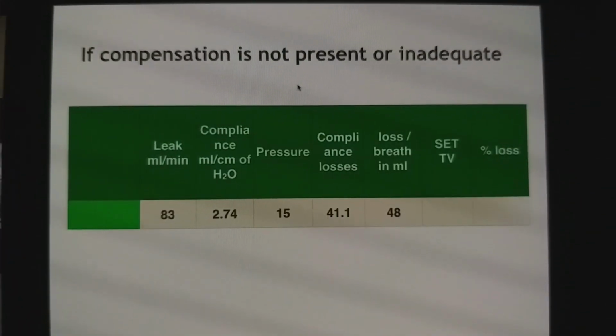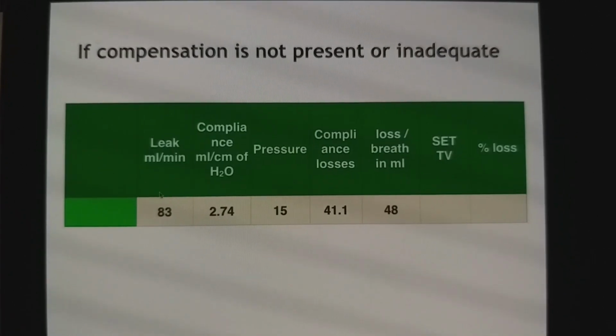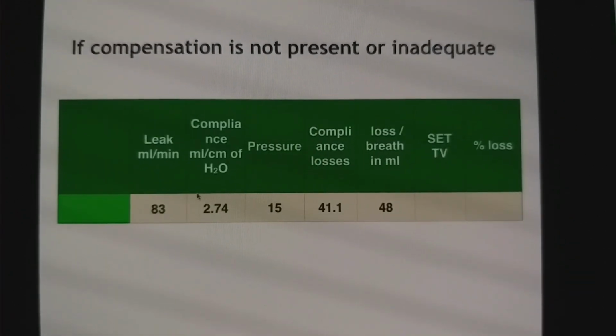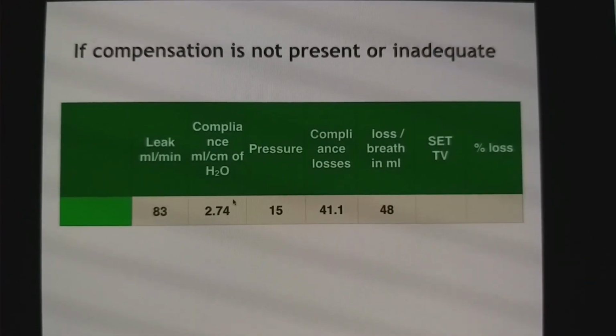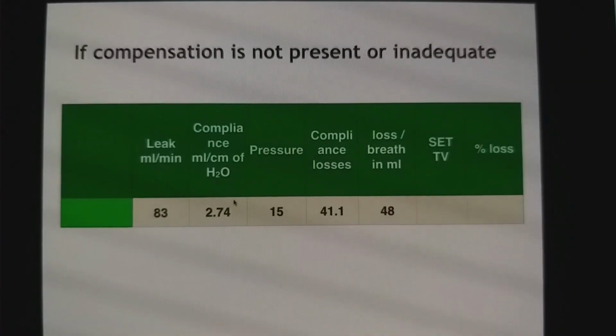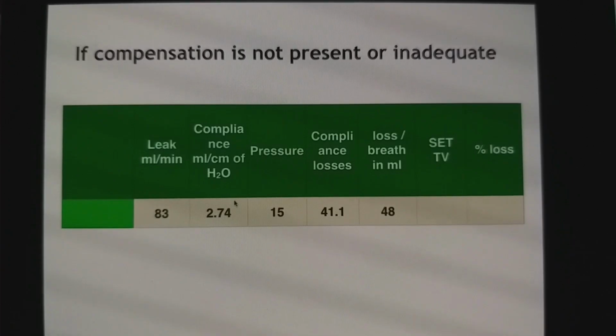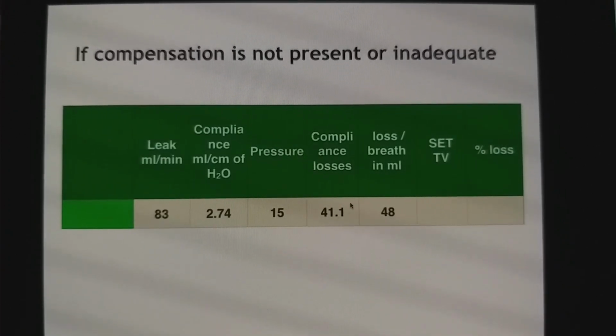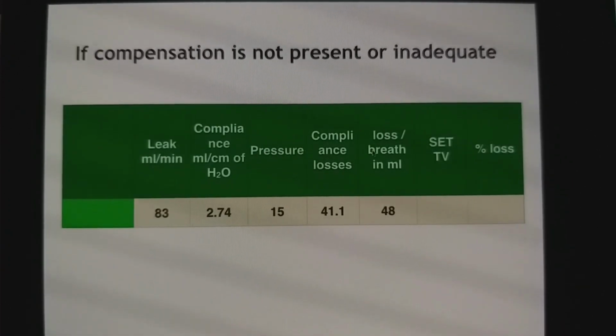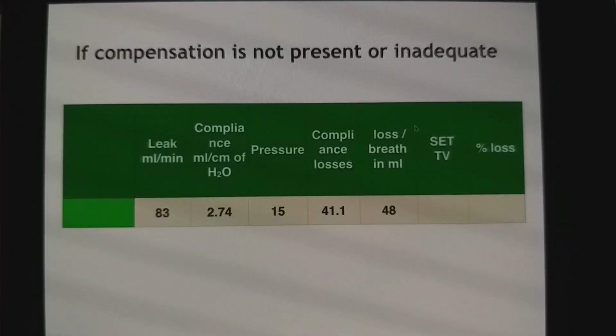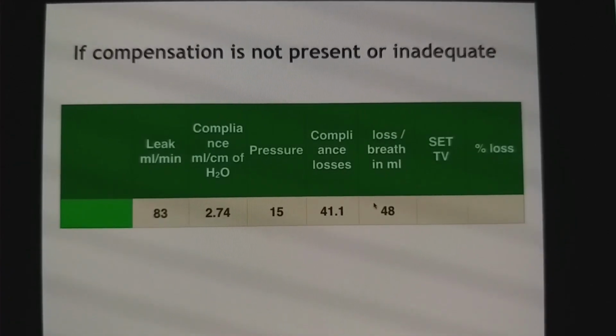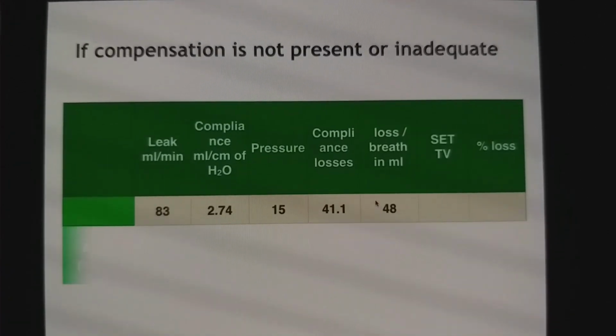Now let us look at the situation. This is the result which I showed you. The leak was 83 ml per minute and the compliance was 2.74 ml per centimeter. So if I am ventilating at a pressure of 15, what is the compliance loss? It is 41 ml, and with the leak per minute, the loss per breath is 48 ml. So every breath there is a loss of 48 ml.